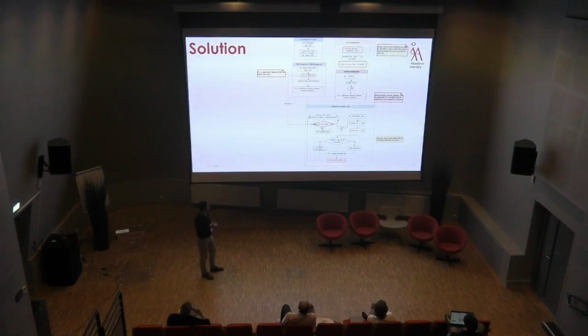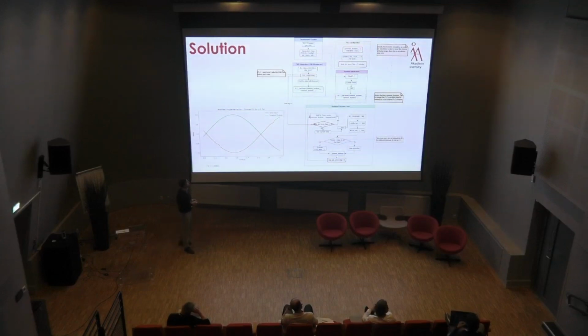The idea that we implemented here is to add into the runtime loop of the PLC program a flag, which sends a notification once the inputs are sampled and the logic has run. Don't wake up until you have additional inputs. With this modification in the runtime loop, we have a better, more stable response from the control logic. Not the one we had before with steps, but a smoother one, apart from this fluctuation, which is related to the non-deterministic behavior of the PLC logic.